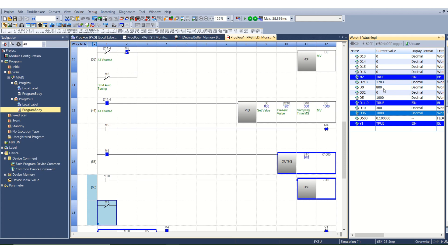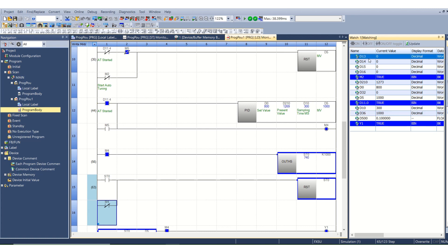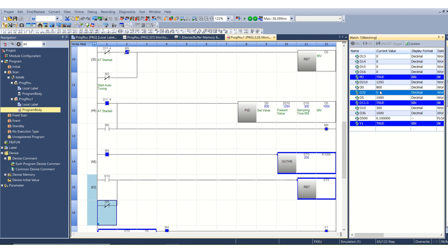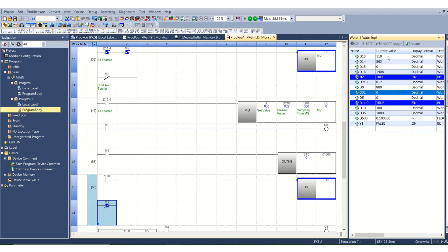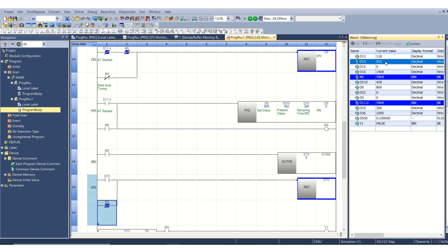Once the auto-tuning is complete, D11.4 will turn off and the value will show here in D13, 14, 15 and 16 according to your heater response. As you can see the auto-tuning is complete now. The value of P is 118, I is 563, and derivative time is 1408.